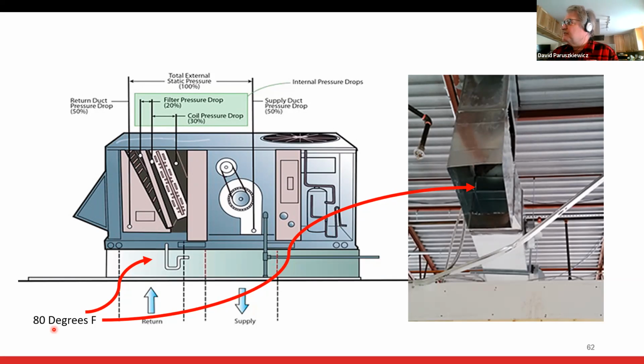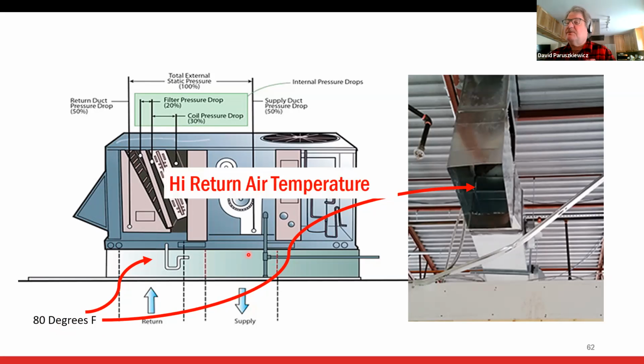I can't tell you how many houses I was in when I was a newbie, a 1,200 square foot ranch with a 140,000 BTU furnace in it, and they cycled on the limit. The equipment didn't know any better. Nowadays, we do know, and it won't do it. So this is an issue. That return temperature is too high. That's an issue.